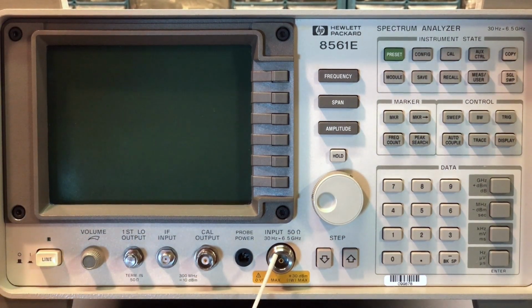Right here is the main RF input, so you can see, of course, it's a 50 ohm input, 30 Hertz to 6.5 gigahertz. And you can see the note under here, the warning, it says 0 volts DC max. So if this is AC coupled, which is the default setting, it blocks any DC input, and you can actually go plus minus 50 volts DC and it won't harm the instrument. So plus minus 50 volts DC max. If this is direct coupled, you cannot put DC into the instrument. I think the maximum allowed is about 200 millivolts. So if you go above that, you will absolutely destroy the front end of the instrument. It will cause definite damage, and you'll have a very bad day because it's extremely expensive to repair that kind of damage.